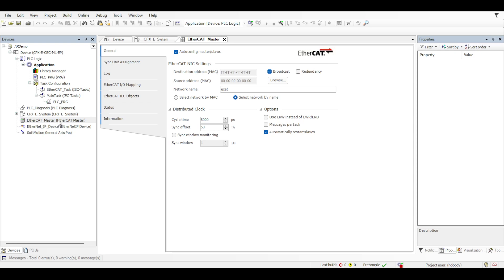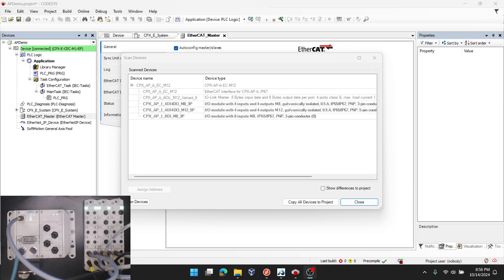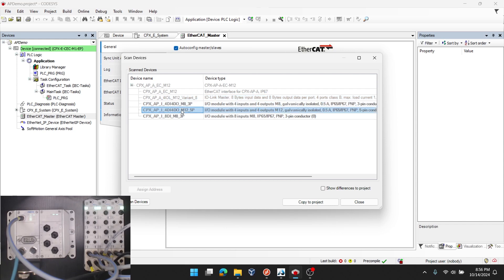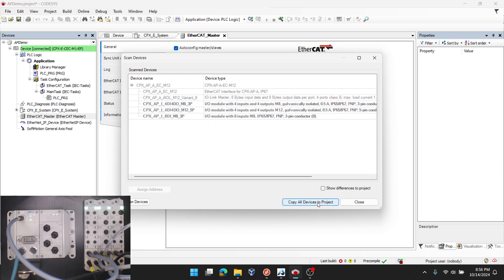By right clicking on EtherCAT master, I click scan for devices in a context popup. After waiting for a few seconds, you can see that I get the APA and API detected. As shown in the bottom left corner, the first module is the APA EtherCAT field bus module, then the APA 4 IO link module, and then three API remote modules.